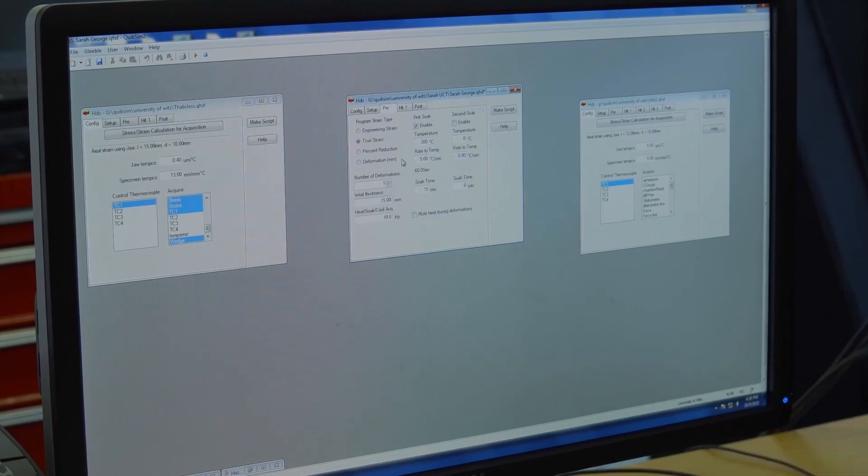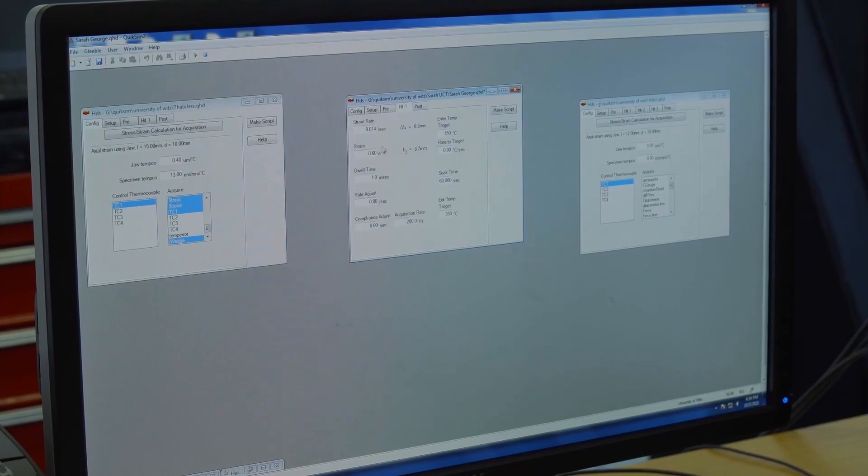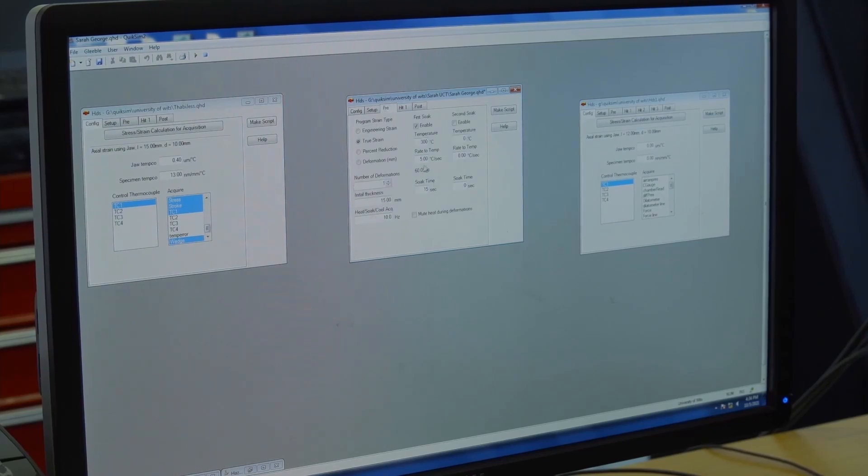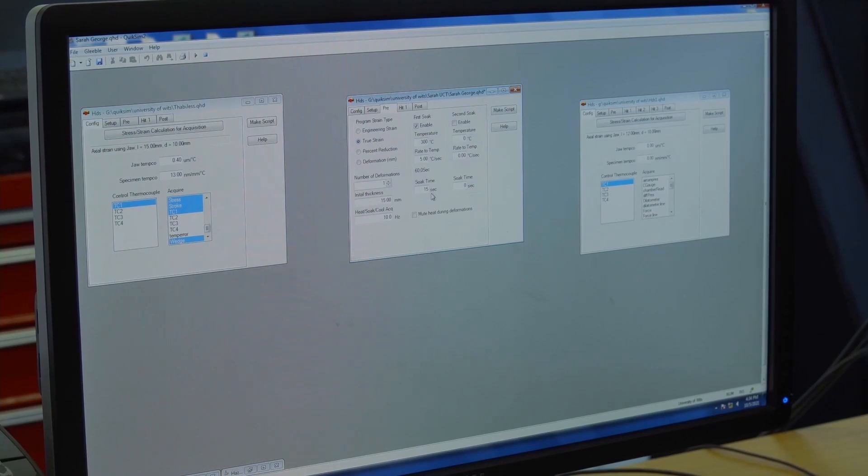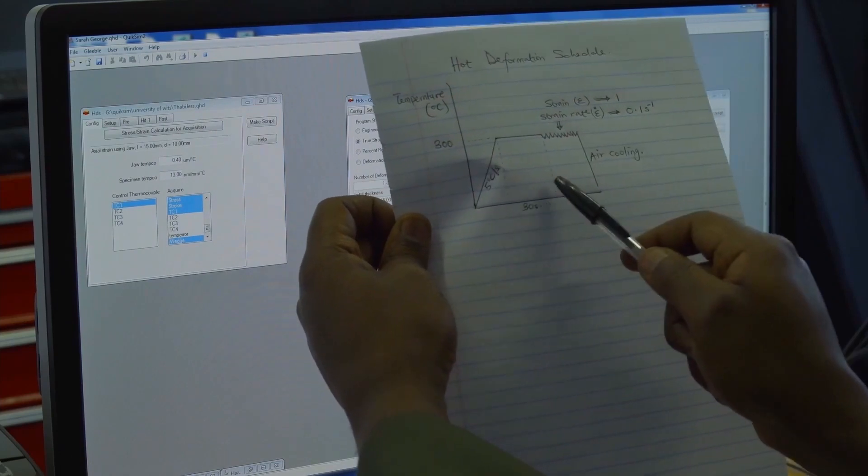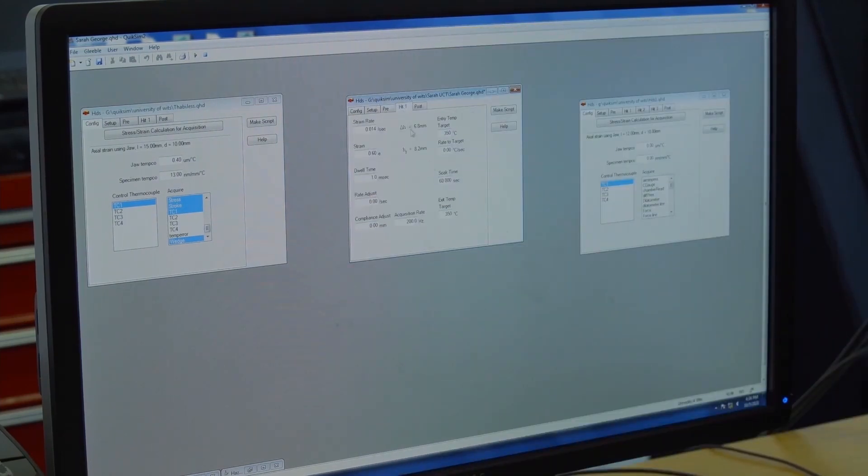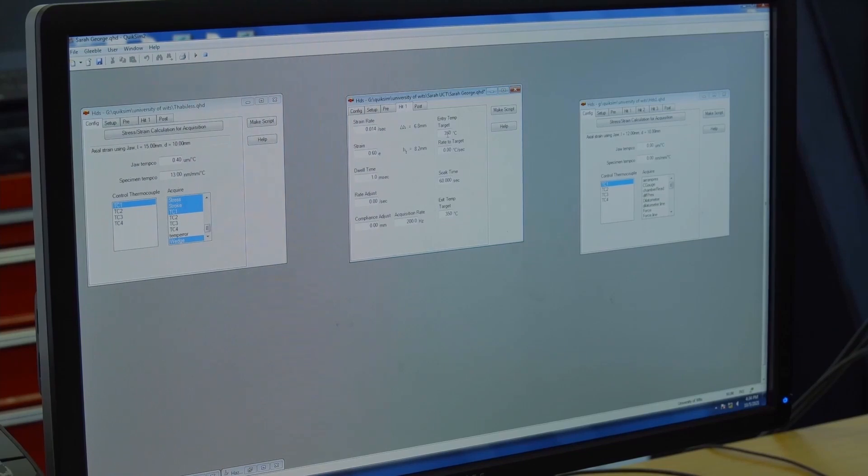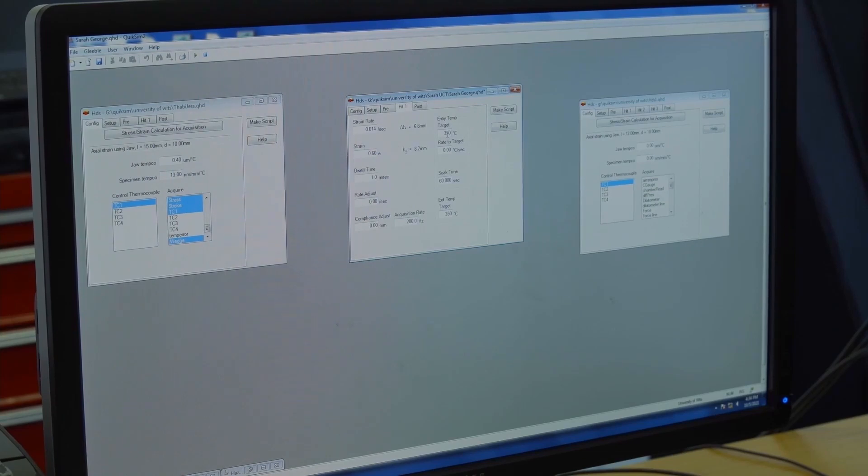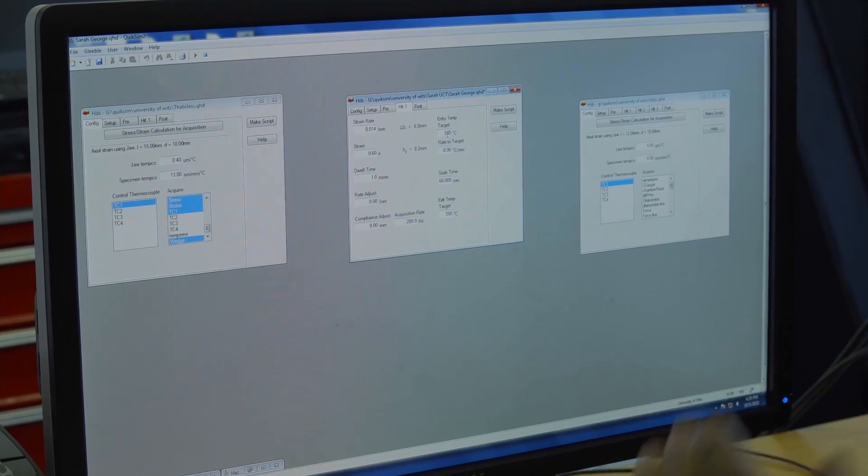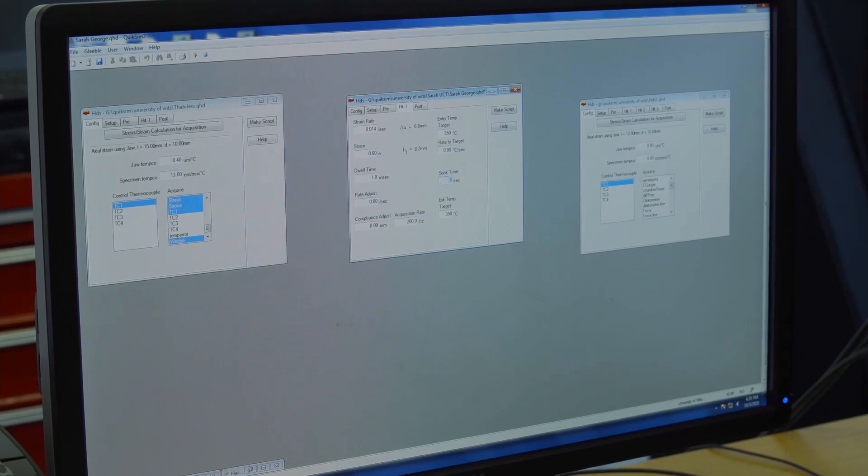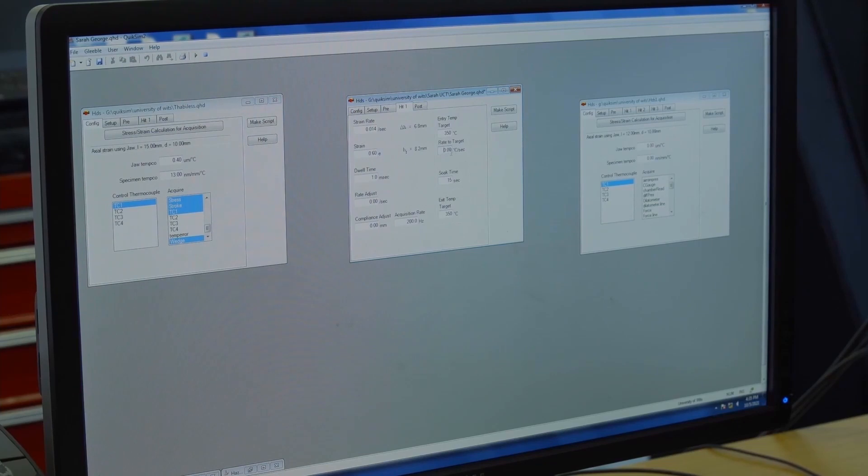I have soaked for 15 seconds, and the diagram is asking me to soak at this temperature for 30 seconds. The reason I am dividing that into two is because when the Gleeble is ready to carry out the deformation, you want it to notify you. When it notifies you, you want it to soak for like 15 seconds before the actual deformation. That's why the remaining half of the 30 seconds, I'll put here as 15.